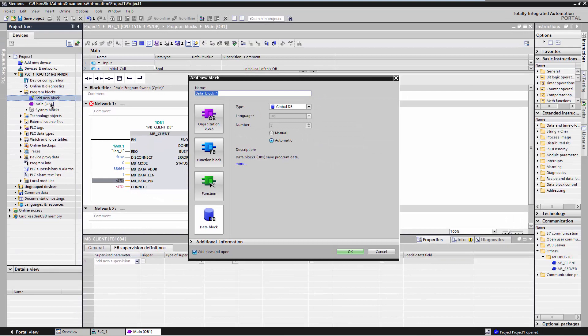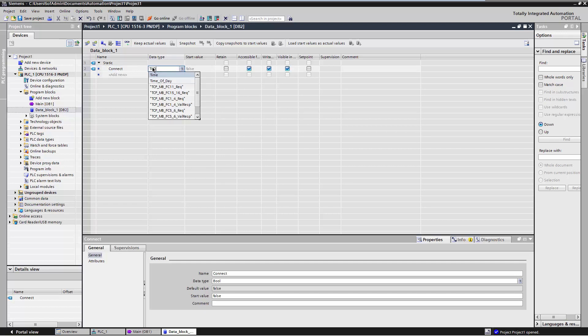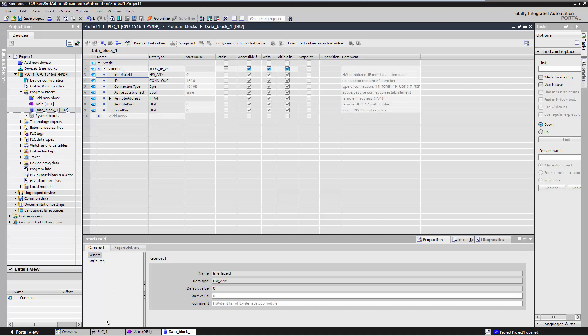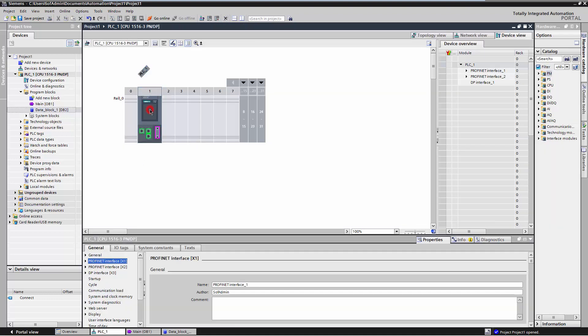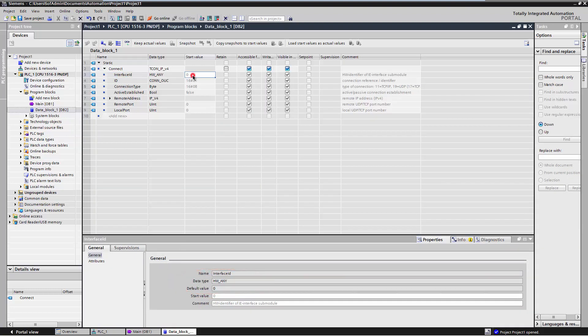To do this, add a global data block. The variable for describing the connection is of type TCON_IP_v4. As the interface ID, the hardware identifier of the PROFINET interface must be entered, in this case 64. ID is used to uniquely identify this connection. For TCP, the connection type is 11.